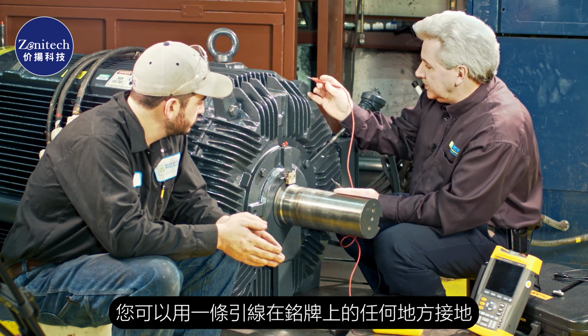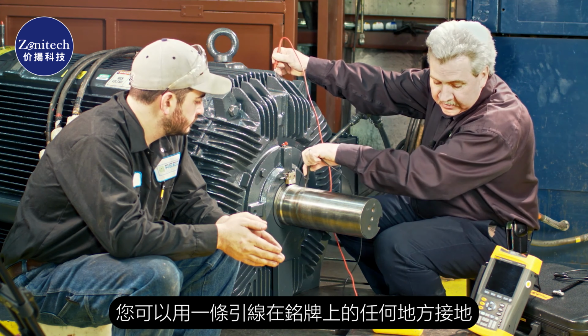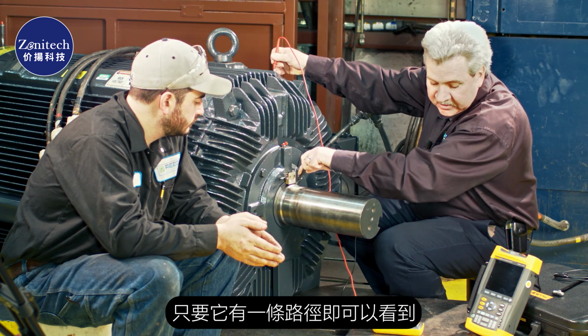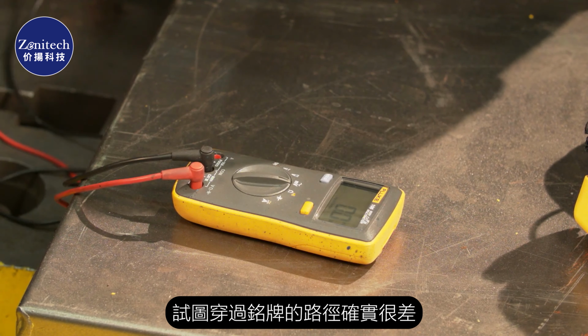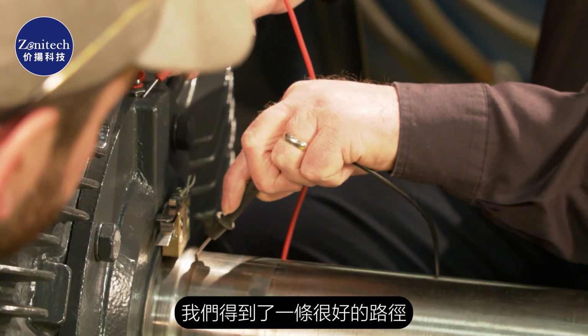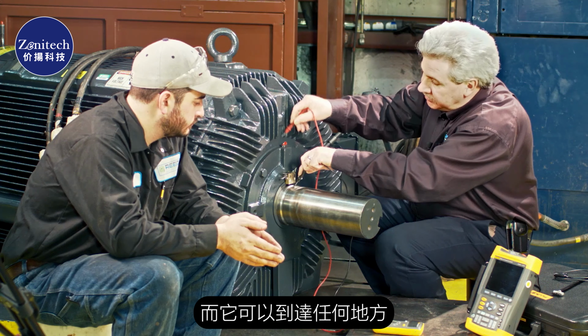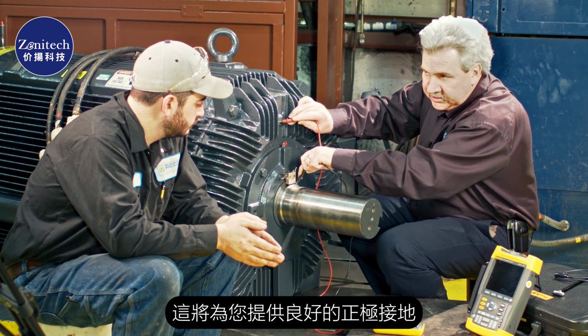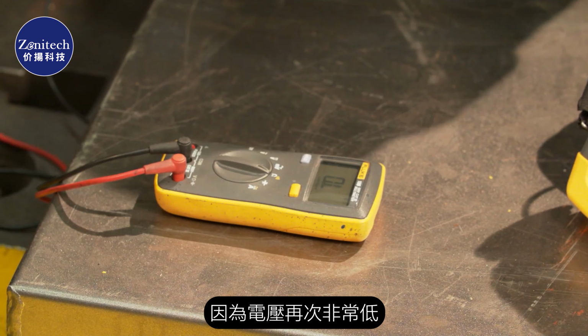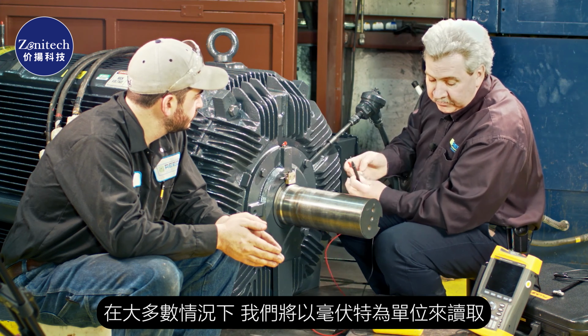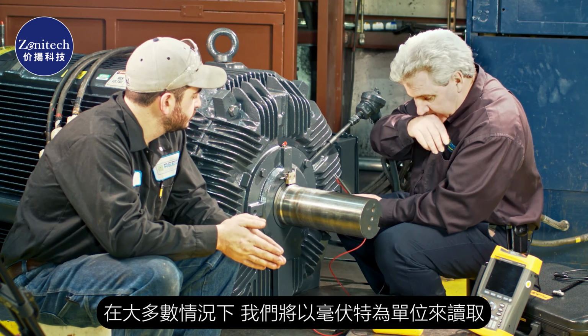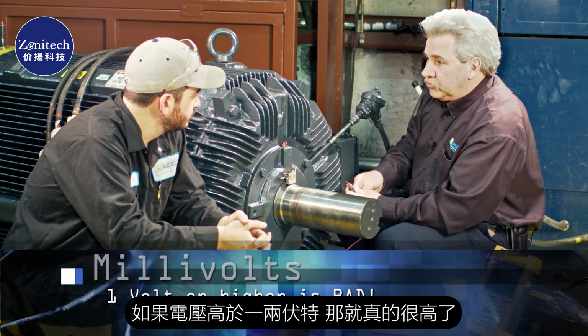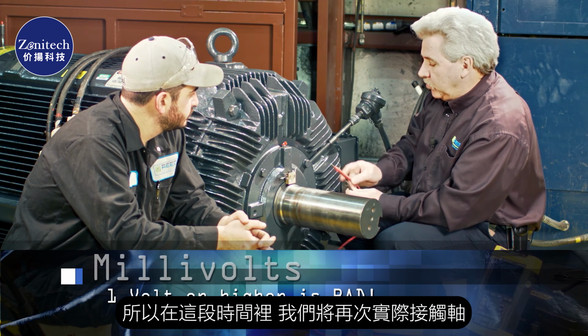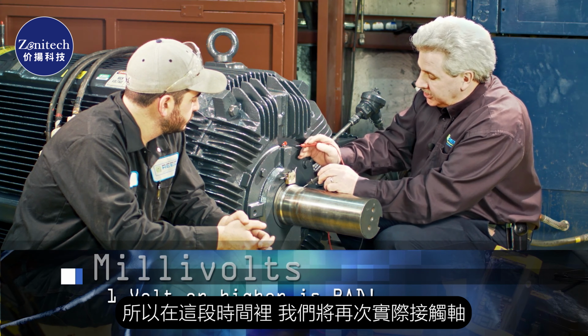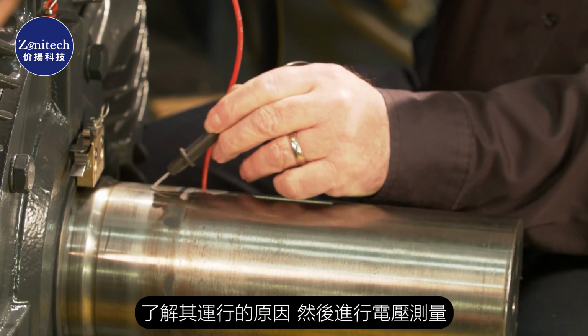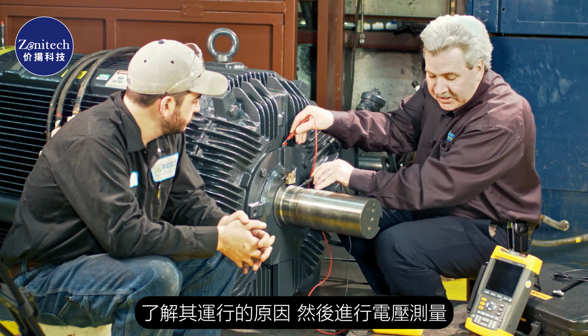You can ground with one lead any place, like on the nameplate, as long as it's got a path. As you can see right there, that path is real poor trying to go through the nameplate. Now it's a little better. Right there at the Zerk, we were getting a nice path, but it can be in any place that'll give you a good positive ground. Because once again, the voltage is extremely low that we're going to try to read. We're going to be reading in millivolts in most cases. If the voltage is higher than 1 or 2 volts, that's really high. Okay? So during the time period, once again, we're going to actually be touching the frame and the shaft while it's running, and then taking a voltage measurement.